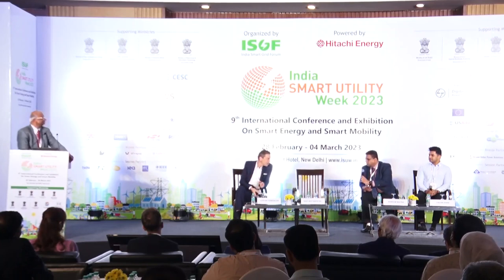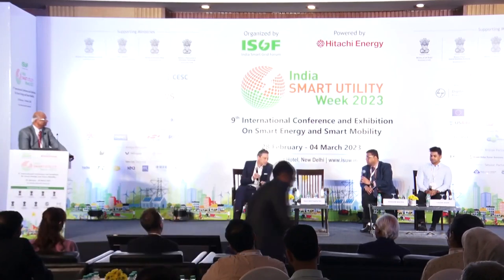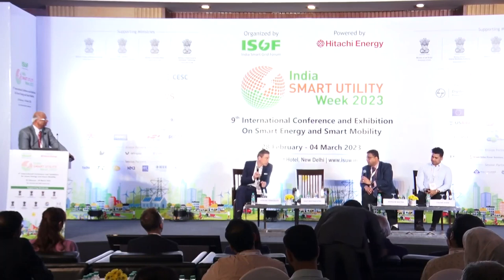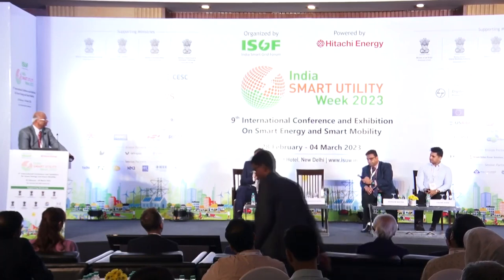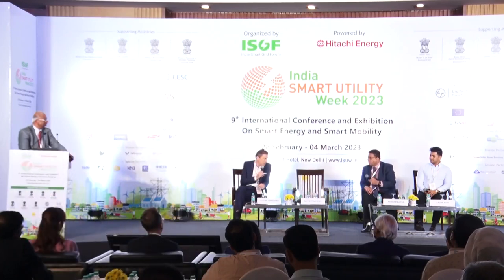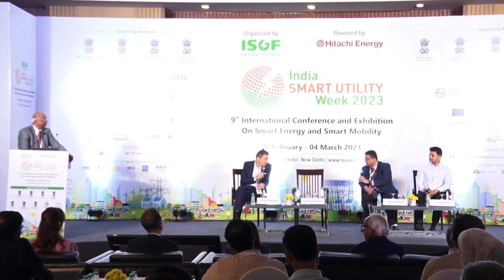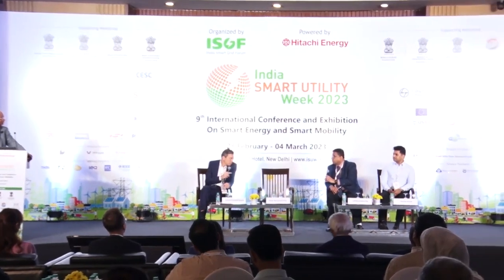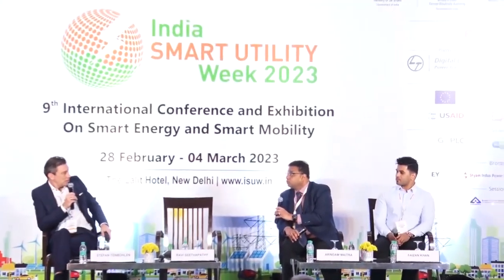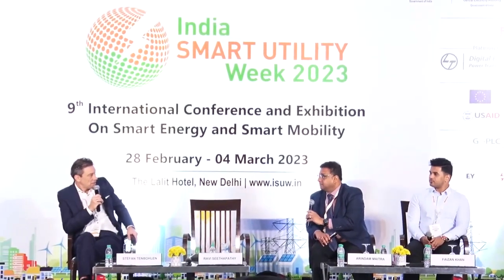Stephen, I have one question for you: where you are, what is the emergency rating of the transformers you use? Because that's how overload is defined, especially for distribution and substation transformers - it's not the normal rating, it's the emergency rating. Some utilities go up to 120%. In the US, and you can tell about Canada, the average across 3,000 utilities is about 150 to 160%. There are some utilities, like consumers, that run it up to 230%. So it varies, but quite a bit.